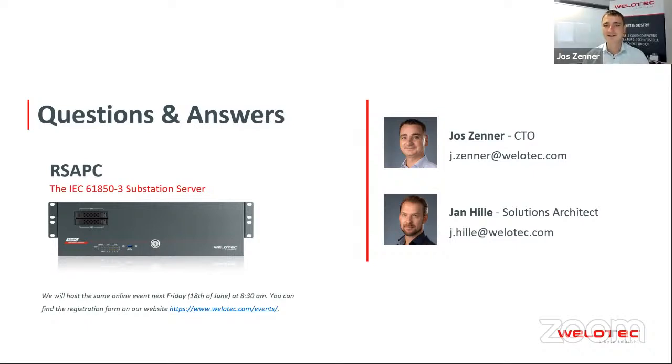Definitely yes. The reason behind this is that it's independent from the software. So you can run a gateway software that is then able to speak those different protocols. So for example, if you need to convert IEC 61850 protocol into DNP3, you can look at the market, and there are a lot of vendors for this. The global players have it within their substation automation systems, but there are also other companies like Kalkitech, for example. There's a company called iGrid.